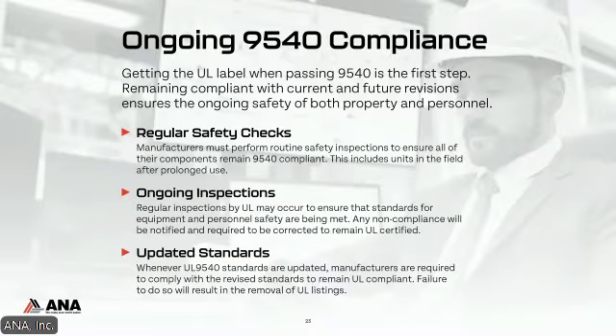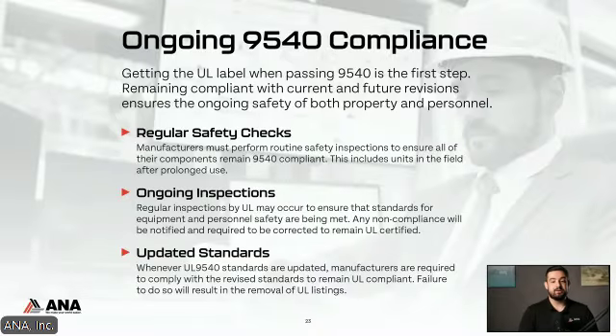So once you pass all your 9540 testing, once you pass all your 9540A testing, your fire propagation testing, everything is well and complies, you will have regulatory safety checks following this, and this will most likely be in the form of manufacturing site visits. This is probably a quarterly visit, but they will check things such as your critical components, that those are still being used and still match up to the report, and that the component is still being built and manufactured in the same way that was specified during the evaluation, right?